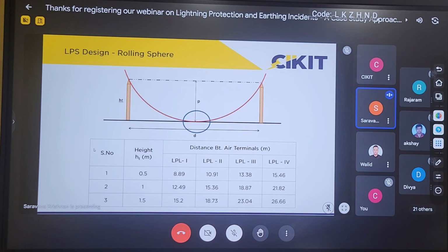The most important thing to keep in mind in the rolling sphere design calculation is that here we are calculating the maximum distance between two air terminals. So the distance between the air terminals and the diameter of protection will be different. In the protection angle method we calculate the radius of protection, but in this method we don't. So I cannot divide a value like 15.46 by 2 and say that the radius of protection for a 0.5 meter air terminal is 7 meters, because here the protection is provided by the cumulative effect of two air terminals. I cannot divide it by 2 to get the radius of protection provided by one air terminal. We have to keep that in mind.